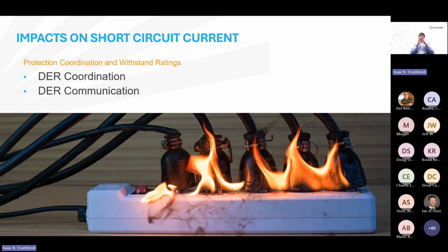I want to stress this is not a wrong design. And for most feeders without distributed energy resources, it is still the correct design to have. However, distributed energy resources shift this historic architecture and cause increases in short circuit current that may exceed existing protective equipment ratings in the lines. Additionally, if not properly designed, a distributed energy resource can supply a fault that is otherwise isolated from the grid, creating unstable islands. As you can imagine, that specific scenario is incredibly dangerous. So, what do we do? How do we mitigate this?